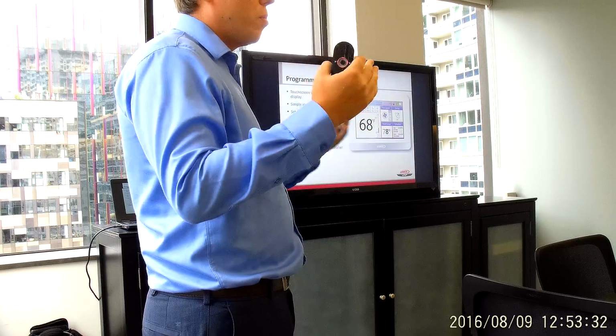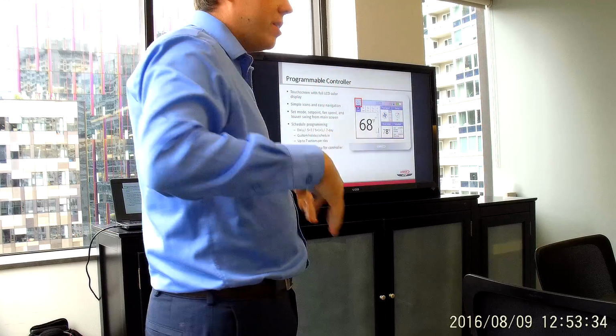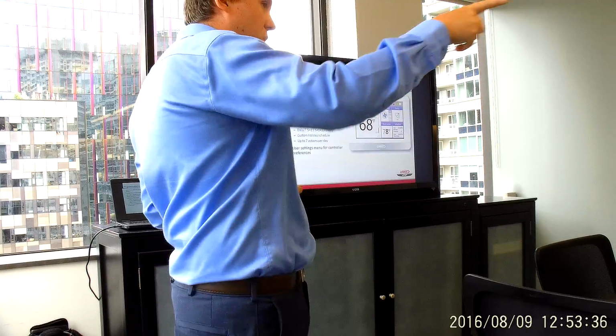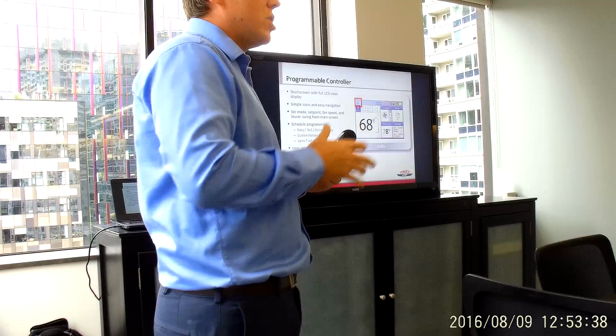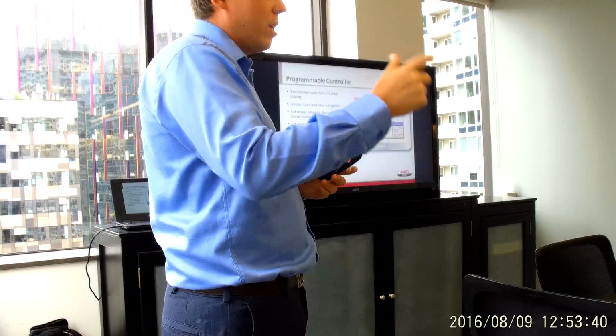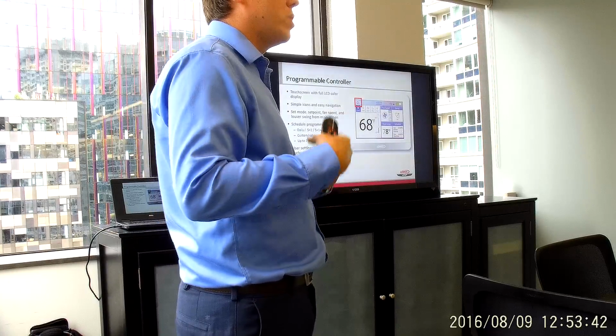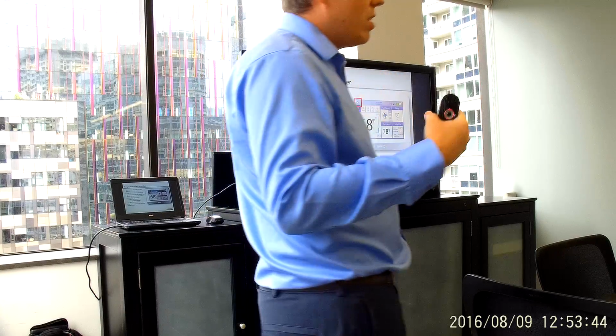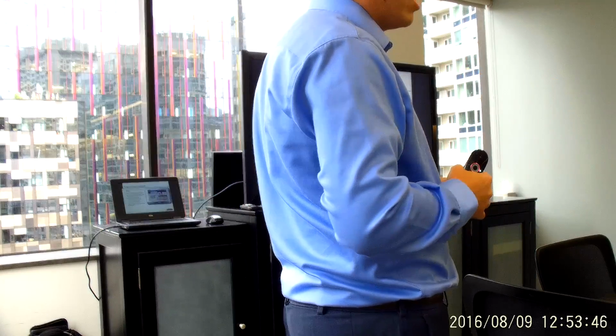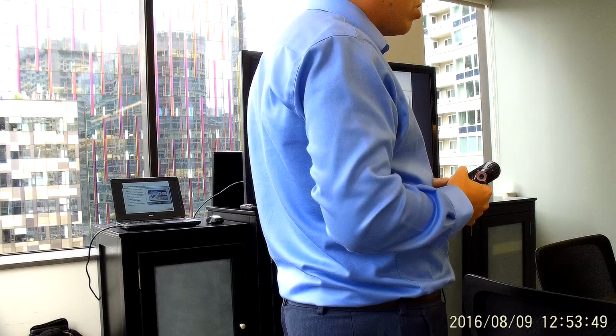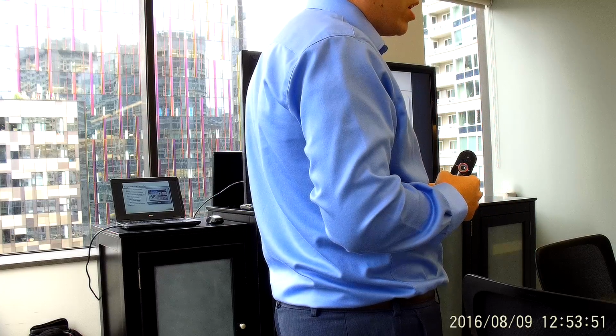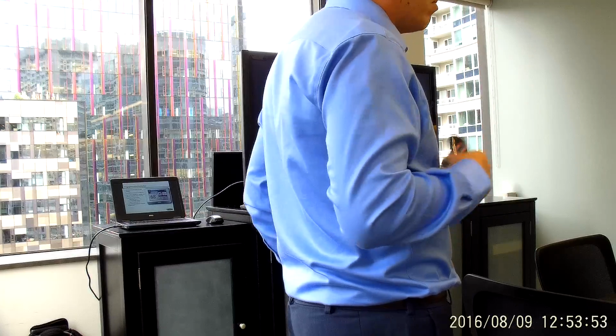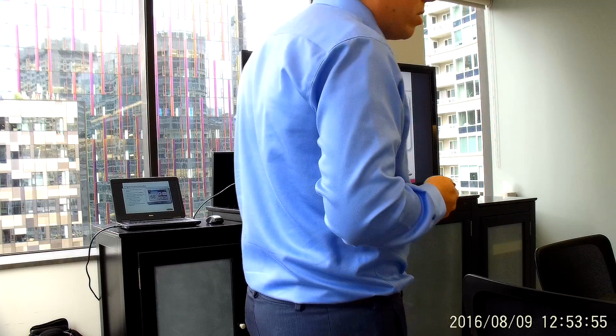Where you would have to compensate for what's actually happening in this space, what they're feeling on this end versus what they're feeling on that end. In this case, you can recalibrate it to suit that temperature difference, and you can play around with that to make sure that you're actually receiving and sensing the temperature that you should be sensing if you don't have a return air sensor or a space sensor associated with that. So you can recalibrate that and make sure that the system operates and works well.